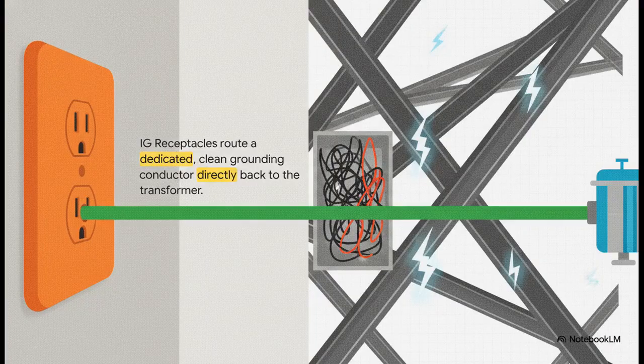But here's the catch. Creating clean power isn't enough if you don't deliver it cleanly. That's why theaters utilize isolated ground, or IG receptacles. Normally, the green ground wire is bonded to the metal junction box and the structural conduit, but an IG receptacle completely isolates the ground terminal from the metal box. It routes a dedicated, insulated grounding conductor all the way back to the isolation transformer. This keeps your super-sensitive audio and video signals totally isolated from all the random structural noise and leakage currents traveling through the building's steel framework.